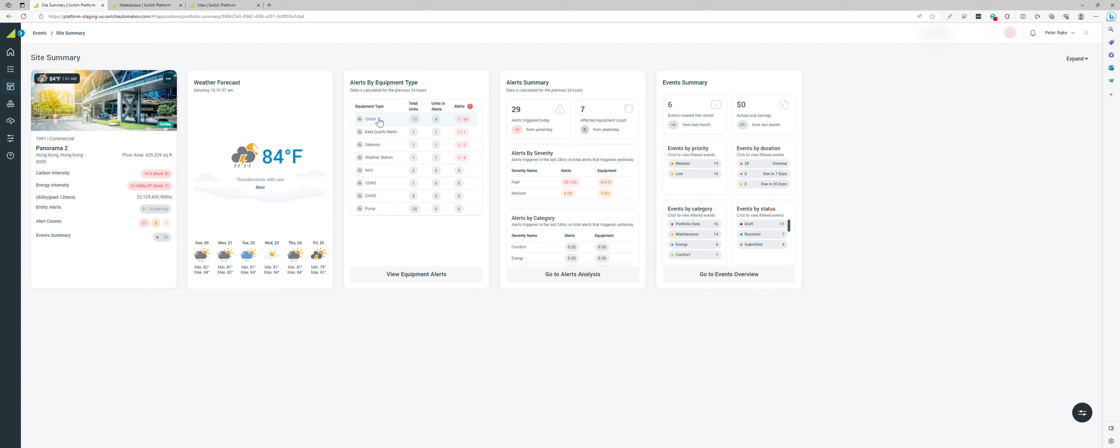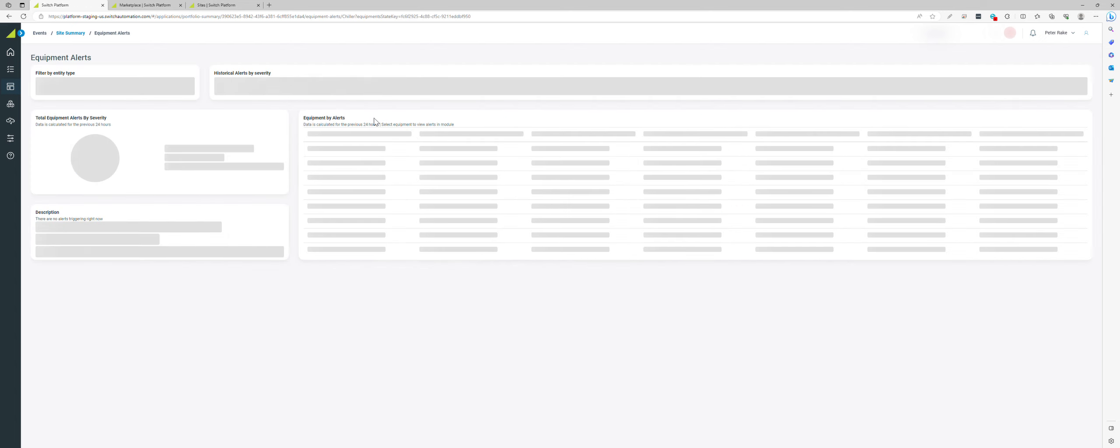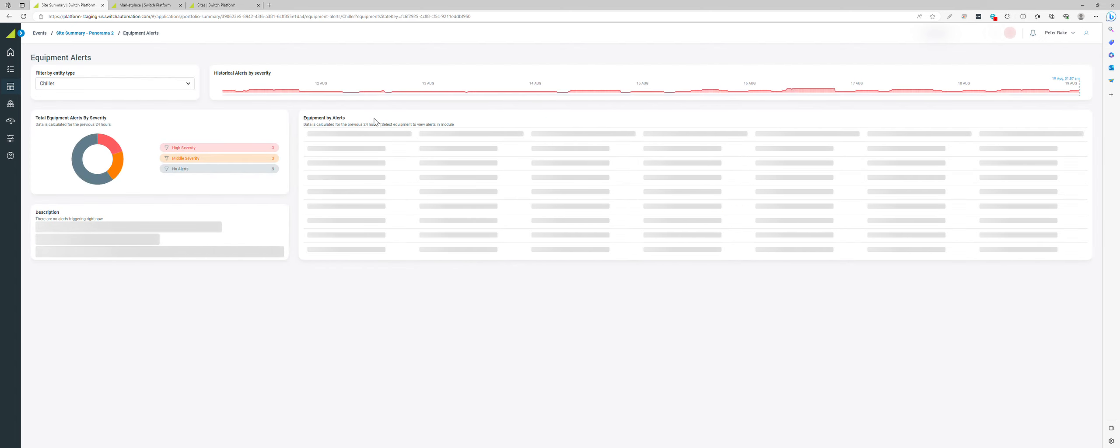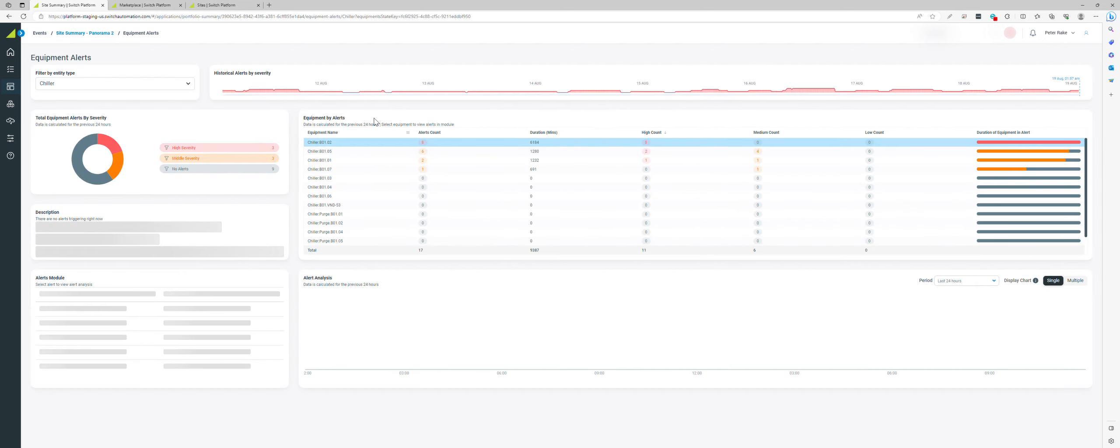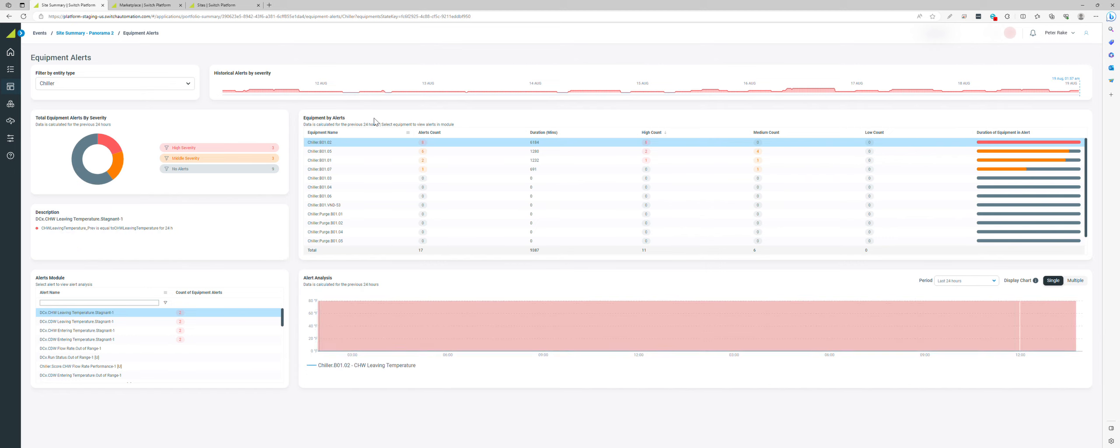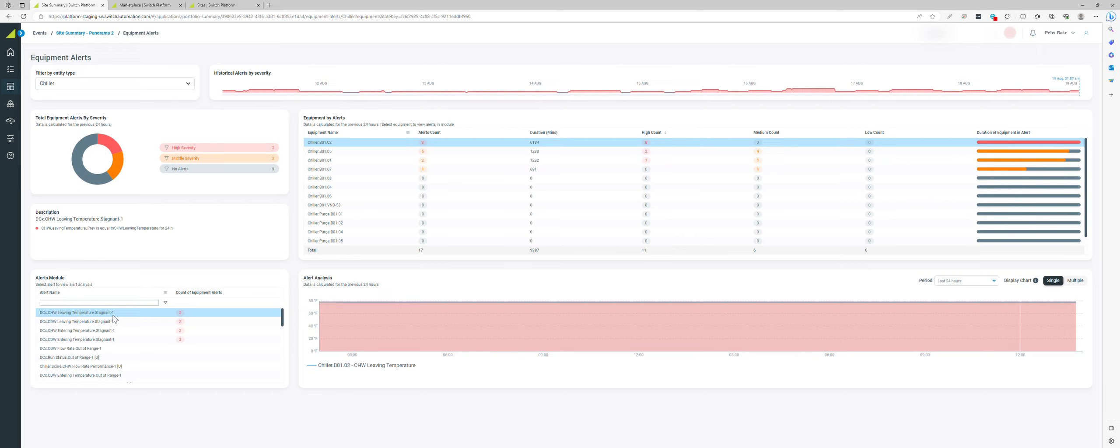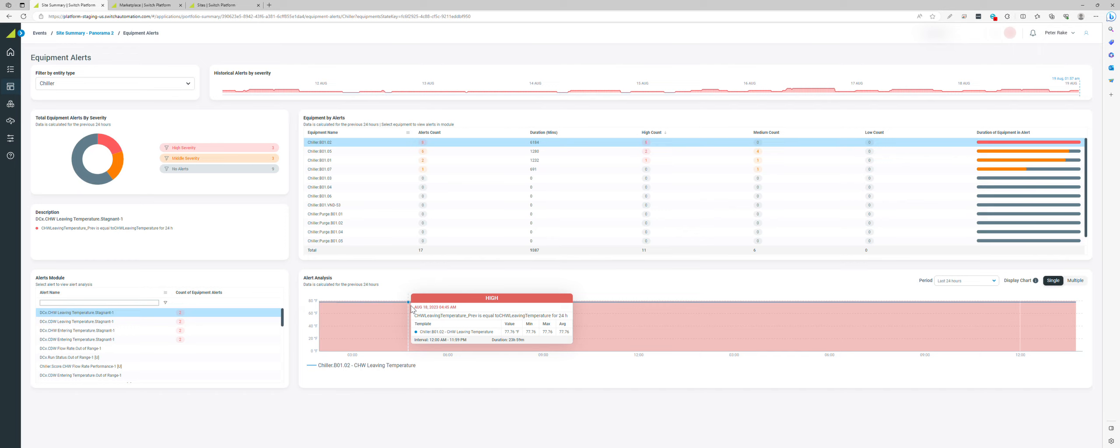Jumping into something more technical, I can have a quick look at the chillers. The chillers are obviously a big part of the building and the feeds of the building. If we've got issues with chillers, that can affect occupant comfort. You can see that we've got data quality issues here where we've got stagnant sensor points coming in from the field.